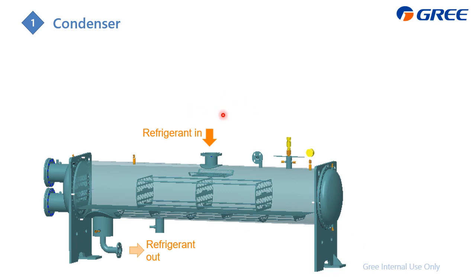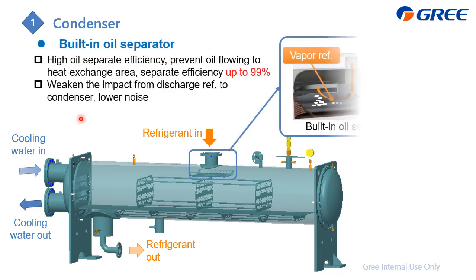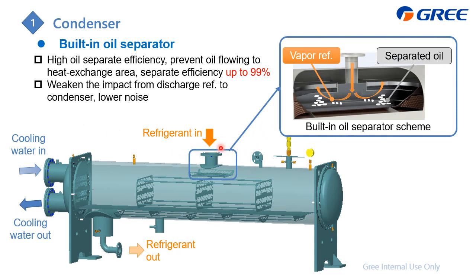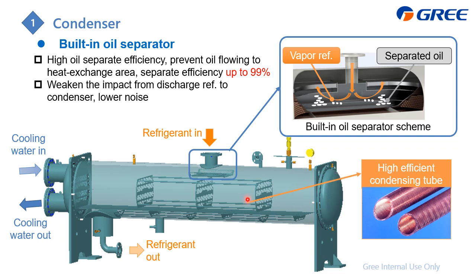And for the condenser, how it works is the refrigerant flows in from the upside, then becomes liquid refrigerant, accumulates here, and flows out from here. And here is the cooling water in and cooling water out. Just pay attention to this area. This is the vapor, which is the gas refrigerant from the compressor. It will hit this separation portion, and then the oil can be separated. The efficiency is also very high, up to 99%, and this can also lower the noise. Also, inside it are the tubes, and you can find that the surface is not smooth, which means this can raise the heat transfer efficiency.